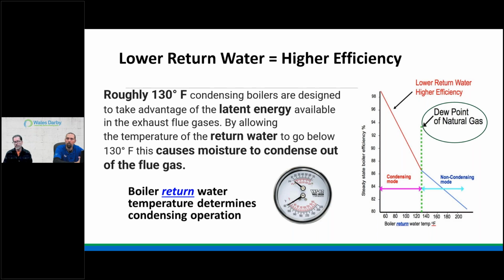And that's the truth. We are not achieving the efficiencies that we see on a label on the piece of equipment that we mount on the wall. So it's 130. At roughly that 130 mark, that's when our flue products start to have the ability to collapse. They go through a change of state from a vapor to a liquid, all right? So that latent energy is something we want to recapture. We're paying for the engineering. The install has been done. This thing has been running, no steady state, it's high limit, short cycling even for what we see on the wall. So the return water causes moisture to condense out of the flue gas, which is the end goal, right?